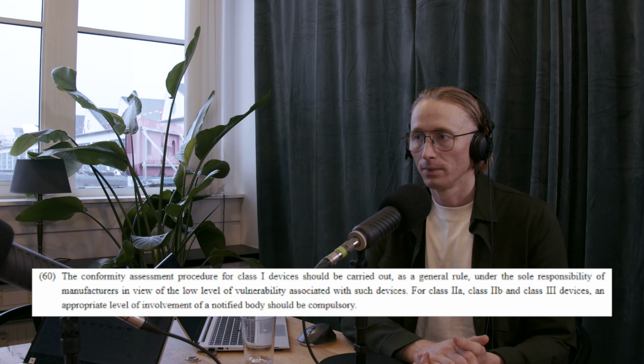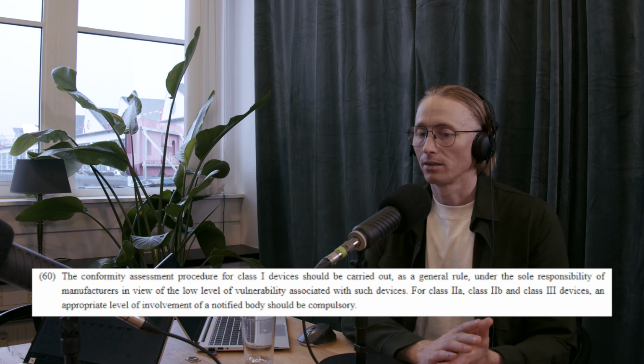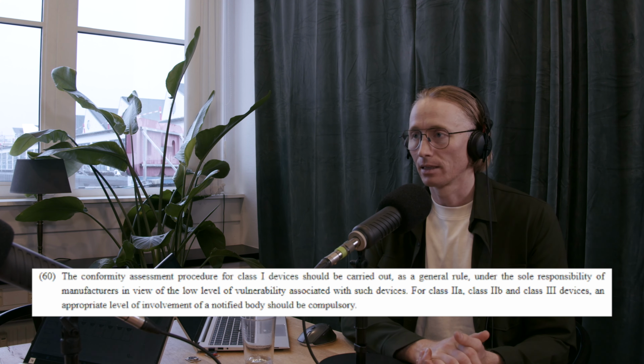It is, and we really need to consider all instances of the specifications of a device. But maybe explain what is the difference between a class 1 and a 2A? Why is it so important? Most of the time, it's due to your approval process. But besides that, it's also well known that class 1 devices need less documentation than class 2A, 2B and class 3.